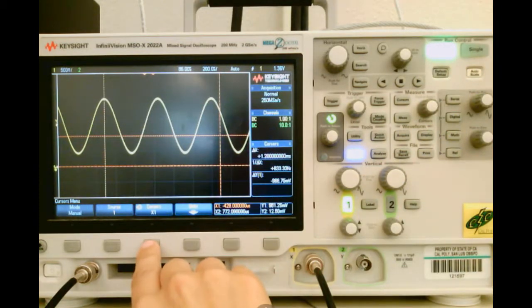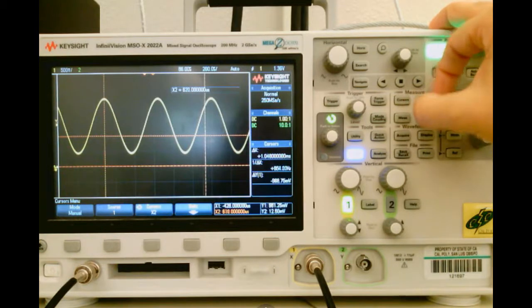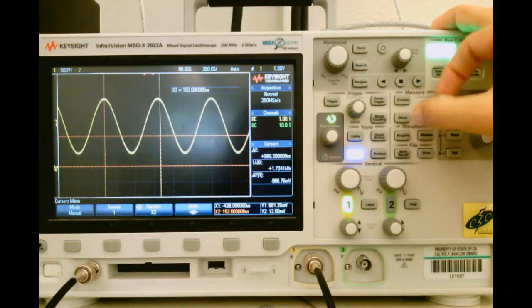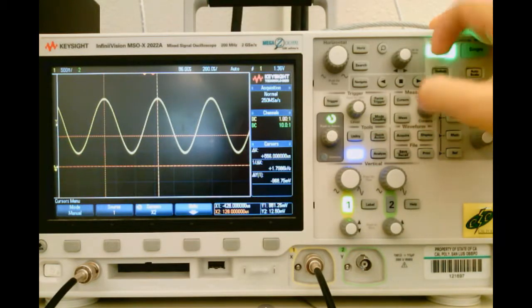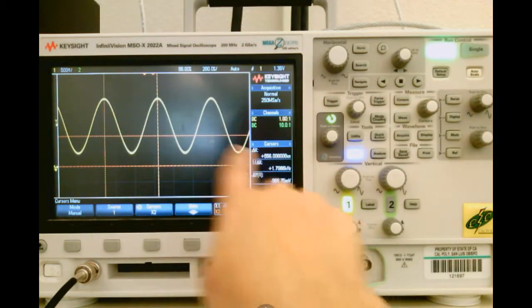Now let's get the X2 cursor to move to the next peak. The difference between the X1 and X2 cursors will now give me the period of my waveform. Looks pretty good. So it says my period, the change in X is 556 microseconds.